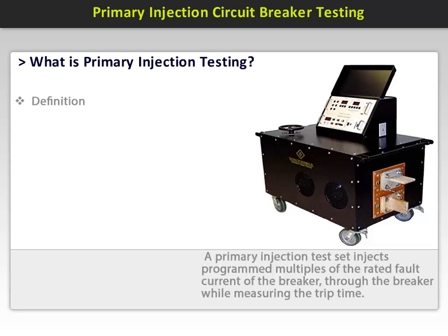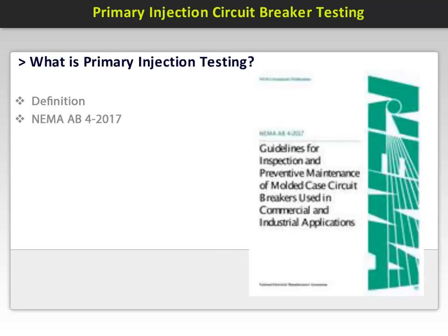Primary injection testing is the optimum standard for testing the performance and integrity of circuit breakers. Shown in this image is the ETI PI6000 Primary Circuit Breaker Test Set. A primary injection test set injects programmed multiples of the rated fault current of the breaker through the breaker while measuring the trip time. Primary injection testing should be in accordance with NEMA AB4-2017 Guidelines for Inspection and Preventive Maintenance of Molded Case Breakers used in commercial and industrial applications.